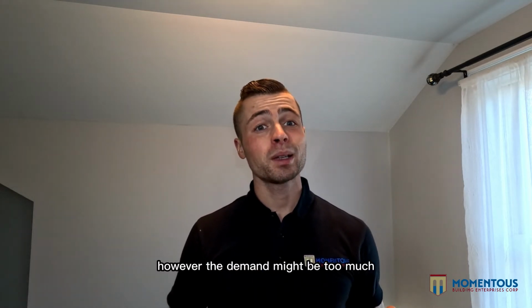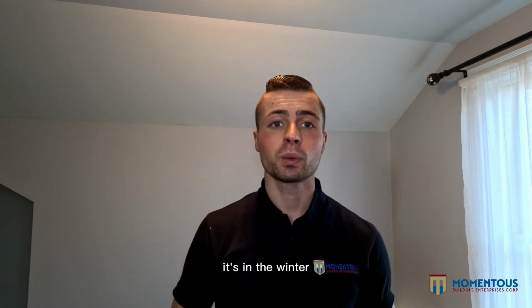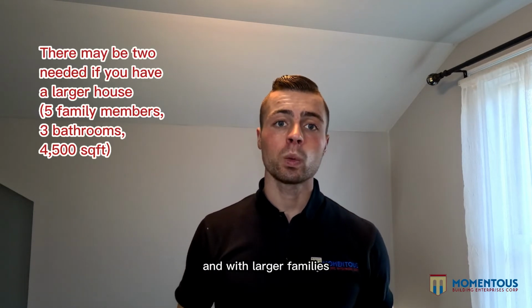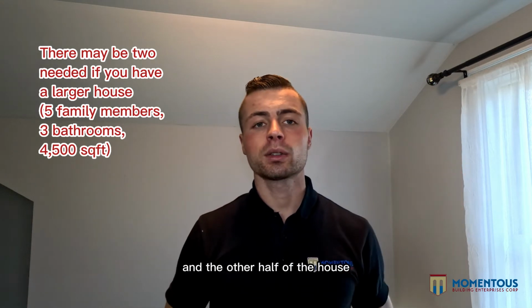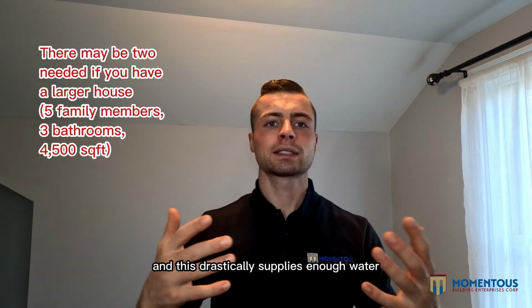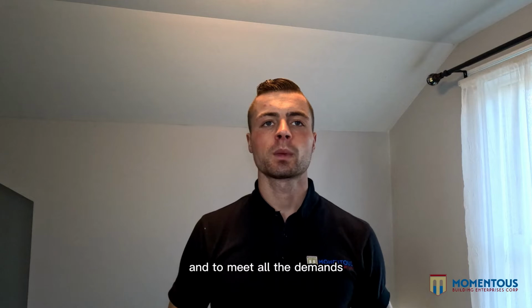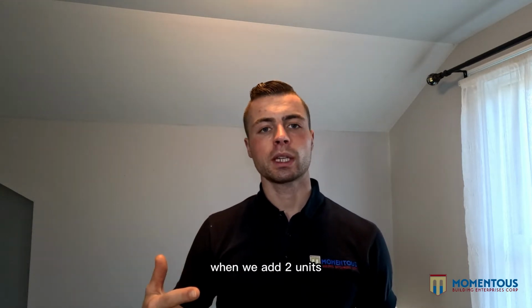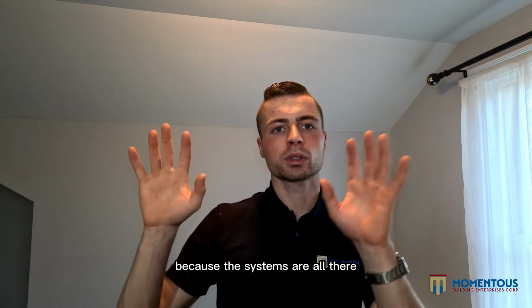However, the demand might be too much if you have your dishwasher going, 2 showers, and it's in the winter so your heat's on. So in some larger residences and with larger families, we actually put in 2 tankless hot water systems. Some might be for half the house and the other half of the house, and this drastically supplies enough water for the rest of the house and to meet all the demands. So that's some consideration to be made. Now, it's not a doubling in cost when we add 2 units. It's usually just the cost of the additional unit with some labor to mount it, because the systems are all there and in place.